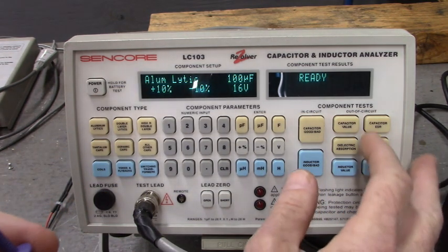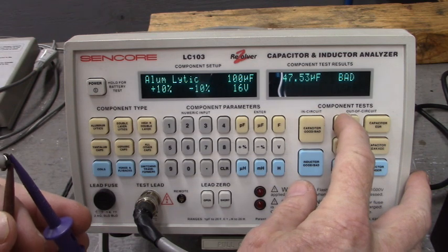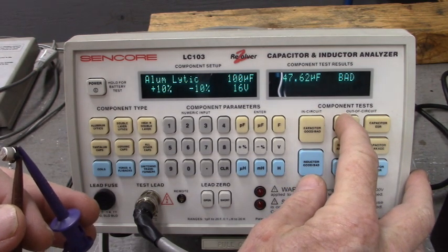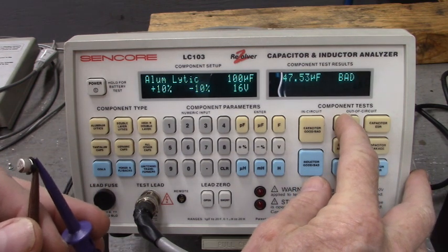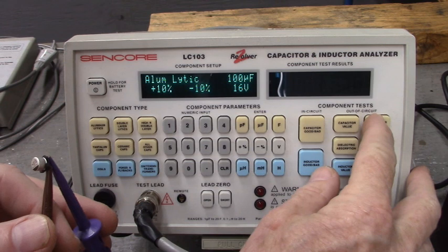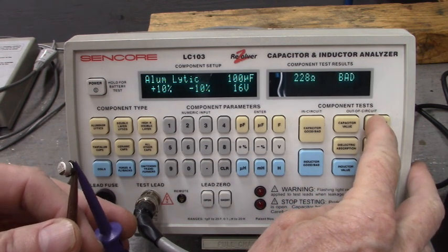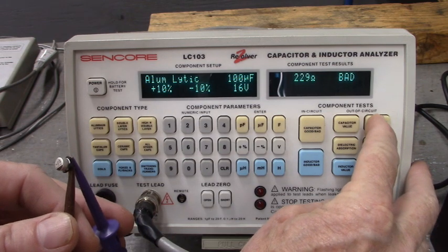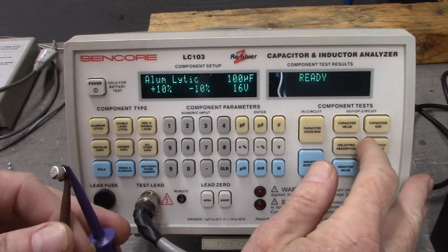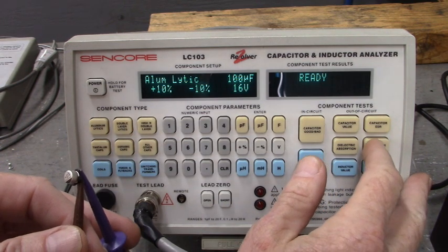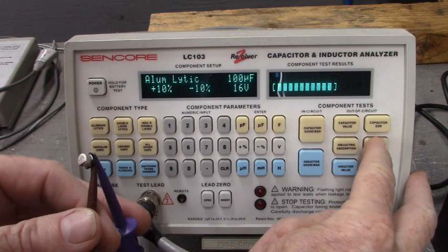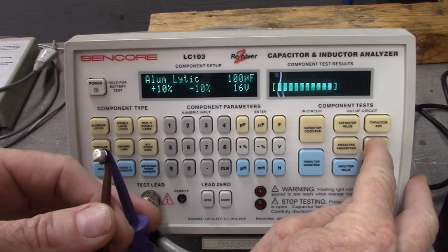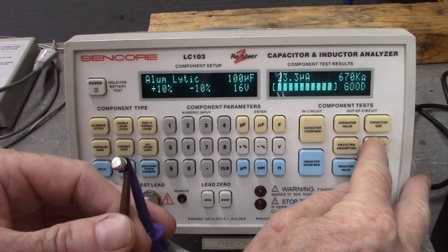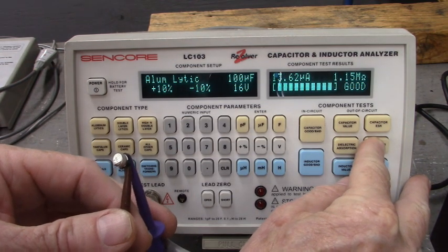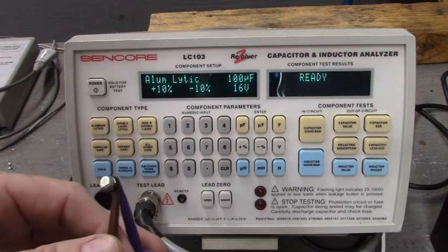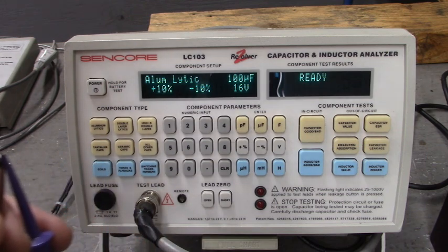Now let's do capacitor value. Look at that. The 100 microfarad capacitor only measures 47.61 microfarad. Here's the ESR, equivalent series resistance: 228 ohms. That might as well be a resistor and not a capacitor. That's why that switch mode power supply was failing in that servo drive. Here's the leakage test: 23.3 microamps, 13.62 microamps. That's not bad. It's not leaky, but the value is too low and the ESR was too high.